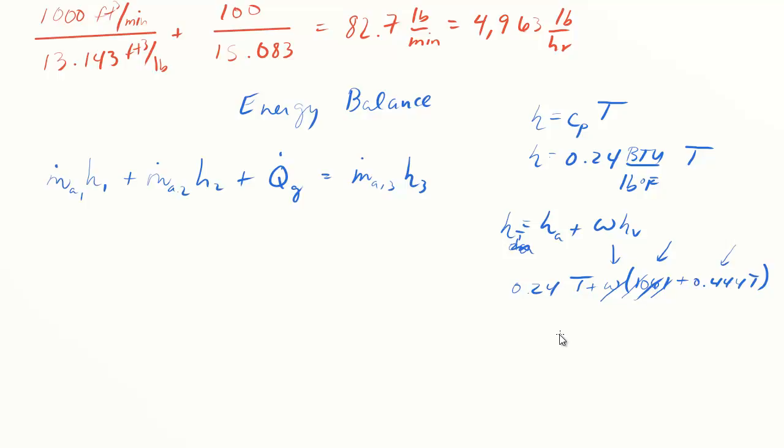Now, this formula is what is used to get the enthalpies from a psych chart or from a program for typical HVAC calculations. So if you get these H values from a chart or program, you will need to use this more detailed equation for enthalpy to get the temperature. You can't just get these H's from the tables and then use the simple one on this side, because you're going to be way off. At 0 degrees F, the enthalpy for the dry air is just zero, but here you would be left with 1061 times the absolute humidity ratio, and so it can make a difference. You can't mix and match. You have to have one definition, either this or this.